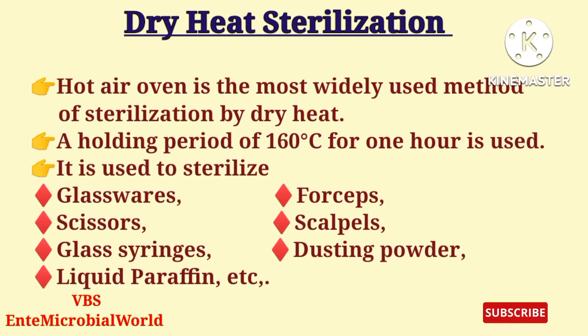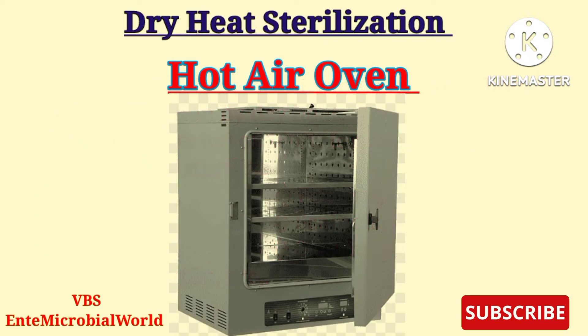A holding period of 160 degrees Celsius for one hour is used in the hot air oven. It is used to sterilize glasswares, forceps, scissors, scalpels, glass syringes, dusting powder, liquid paraffin, etc.